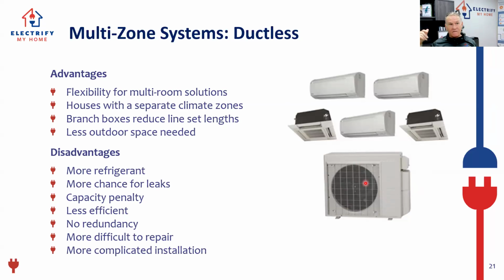It was literally a 50-foot run to the branch box, just right under the spec. And then I had a set going up to one air handler, I had a set going to another air handler, and I had a set going to a wall mount, all off this branch box. That was not a savings of line set length. We did that like 5 years ago when copper was relatively cheap. Now copper is not cheap. We got to think about that too. Less outdoor space needed with these.